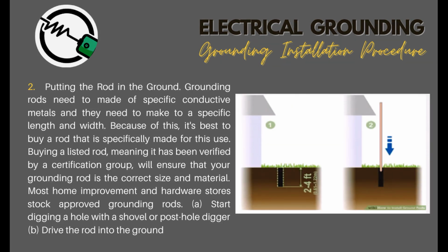2. Putting the rod in the ground. Grounding rods need to be made of specific conductive metals and they need to be a specific length and width. Because of this, it's best to buy a rod that is specifically made for this use. Buying a listed rod, meaning it has been verified by a certification group, will ensure that your grounding rod is the correct size and material. Most home improvement and hardware stores stock approved grounding rods. A. Start digging a hole with a shovel or post hole digger. B. Drive the rod into the ground.